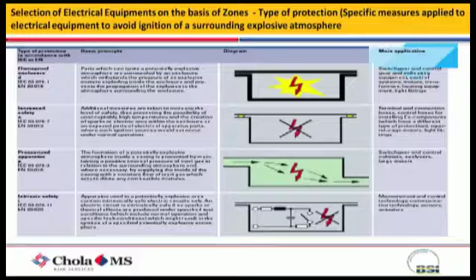That area could be handling some other materials which is safe, or it could be your office space where you might use heaters. In an equipment also you have pressurized equipment, where we send inert gas inside it. It's an ordinary equipment where electrical arcs or sparks could happen, but we force the inert gas inside, going through a closed cycle. So even if there is a spark, it will not allow any arc to happen inside because we are putting inert gas, which could be nitrogen or any other inert gas.